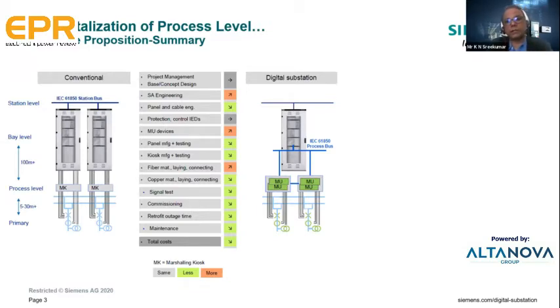Moving to the right to see the digital substation, you can see the green part, meaning whether you use an NCIT or optical CT, you already get digital information from that. You connect it to a merging unit, along with circuit breaker status, control commands and inputs, making the whole thing more digital, shown in green. Then it connects to a merging unit, and from there it's available to a process bus for performing all required functions.